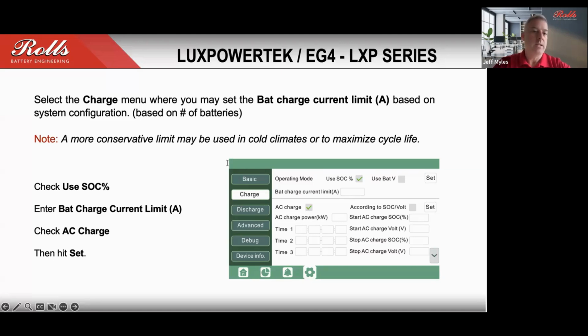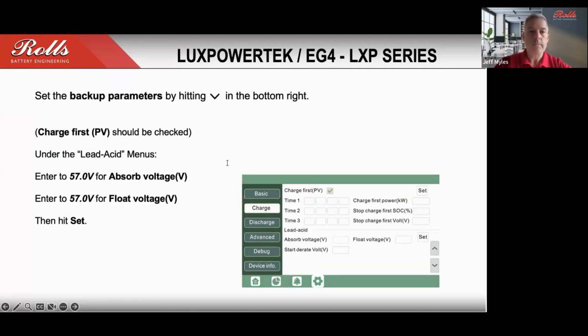One thing that we did note through this process in setting up these was that a lot of the units have a pre-programmed LFP setting, for example, which in some cases will align with the charge requirements for our stackable, but in some cases you will need to tweak it. So we've outlined that at the beginning of the guide, mentioning that the bulk of the settings that are programmed under that profile will work. However, we recommend making these small adjustments.